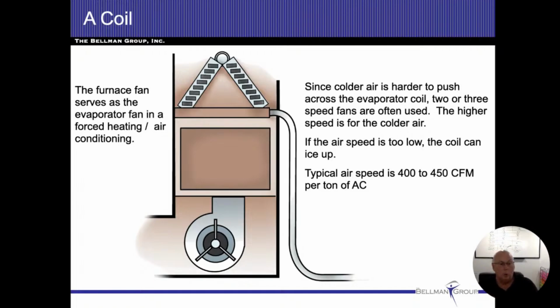All right. So when you're going around and you got the air conditioning running, try to hit every single room and make sure you got a decent airflow coming out of there. Some people, and Mark, if you're still here, I know you're going to know this answer, but some people use a wind or an airflow monitoring device, and I'm drawing a blank on what that's called right now. But they put that over the ductwork, and I kind of like that idea because now we have a definitive number. And then if we have one room that's significantly less than the rest of them, that could actually be an area where we're going to have trouble heating or cooling.